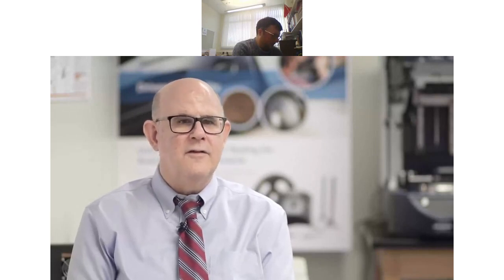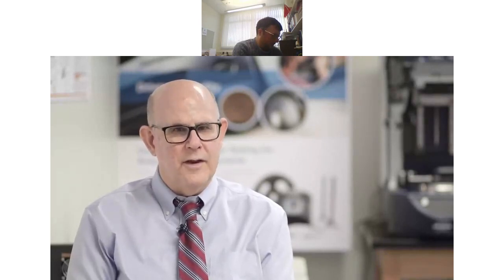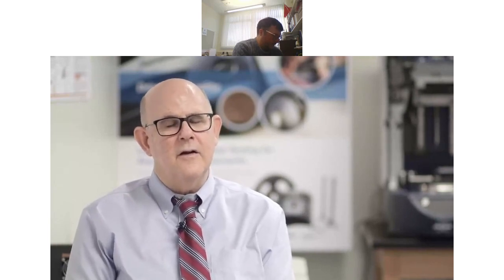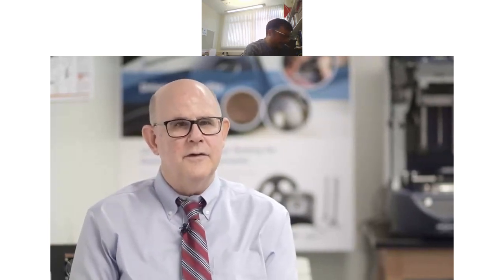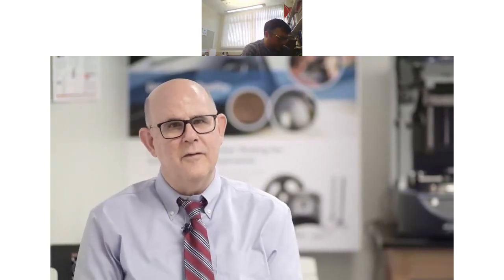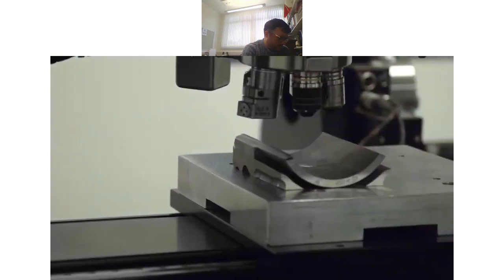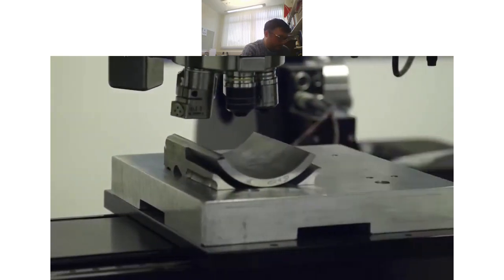The only other thing to watch out for is if the material is composed of any multi-layers of films that are somewhat transparent, then that can cause some trouble since we're using an optical instrument. The light goes through those transparent films and causes some problems, so you have to be a little bit aware of that. Other than that, as long as it can fit under a microscope, that's why I usually say to customers, if you can look at it under a microscope, I can probably measure it.